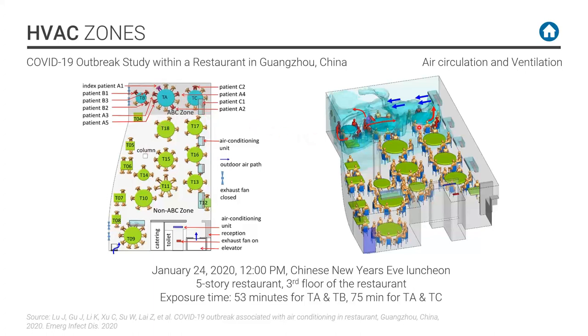So here's sort of an illustration. They used tracer gases. They went in scientifically. They actually did it with the same amount of sun coming through the windows. It was a cloudy day. They wanted to simulate the exact conditions that they could. And what they found is these units on the wall were blowing air, and the flow and direction of the air was such that it just kept pushing the air from the sick person and recirculating. And what they discovered is it was a very high concentration of the virus in this area. So everybody seemed to get sick.